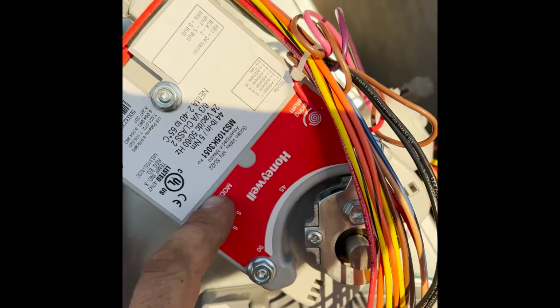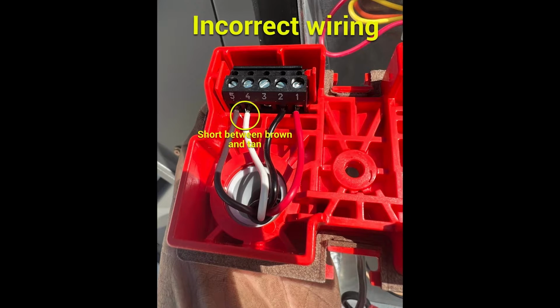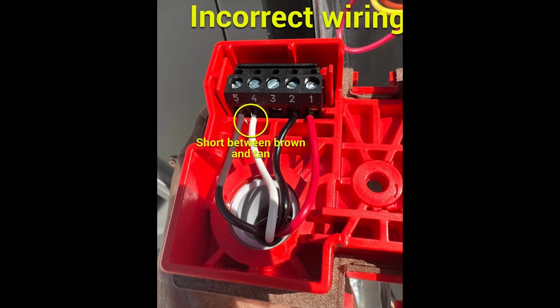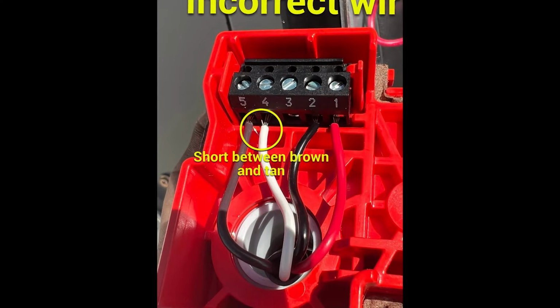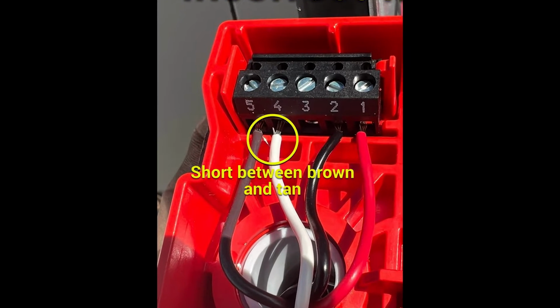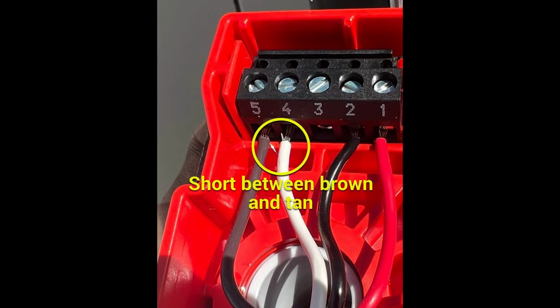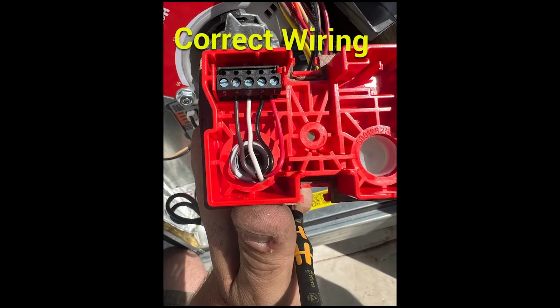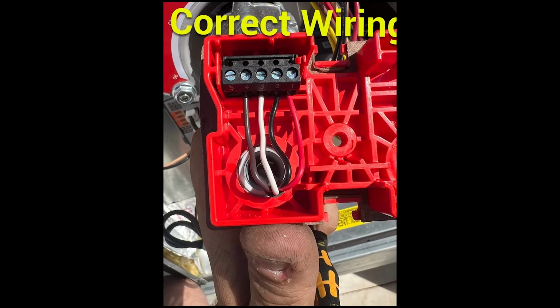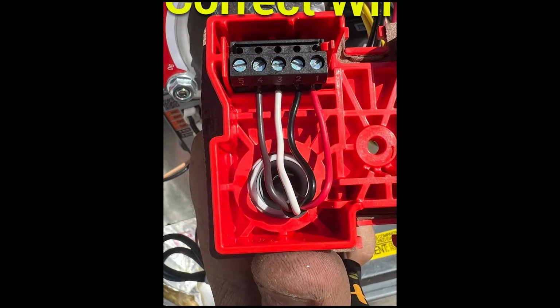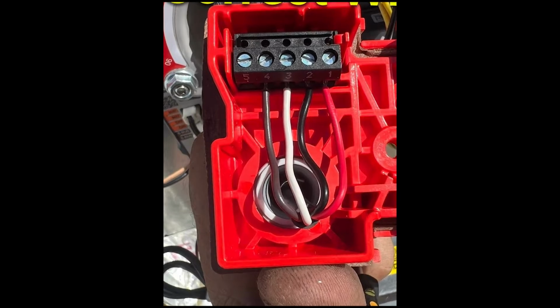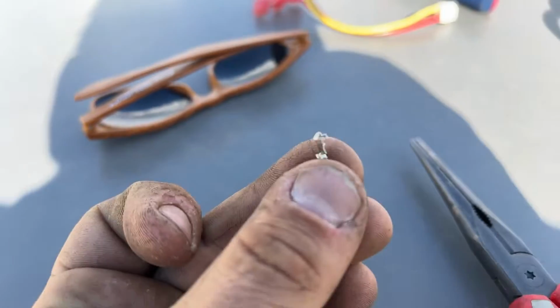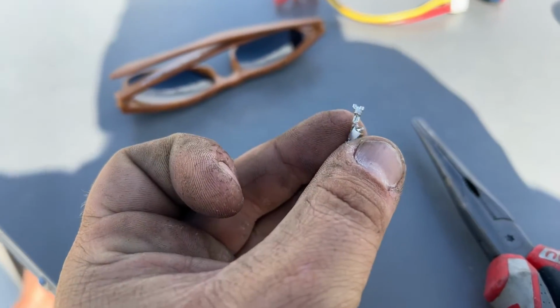So how about that? When we pulled off the back of the motor, we found a short between the two wires that led to that pin. Upon further inspection, most of the economizer motors were actually wired incorrectly. So this is the correct way they should be. We had to go through and fix almost all of them. The Molex pin came out that wasn't crimped well. Just checking all the connections since we're wired up funky.